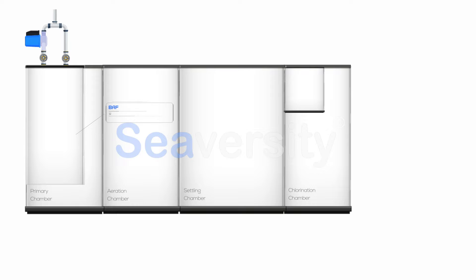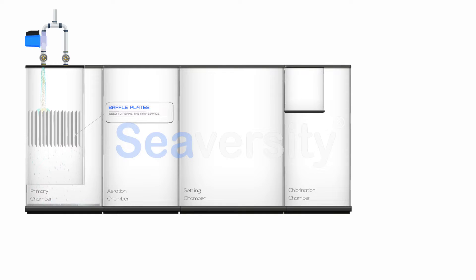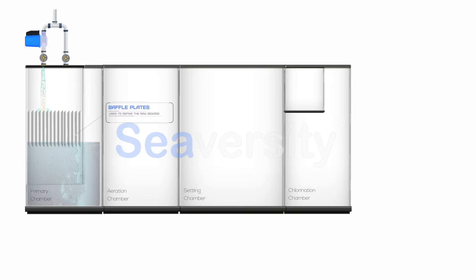The design of the primary chamber, aided by baffle plates, encourages the settling of heavier solids at the bottom and a breakdown of solid waste. This separation is crucial for the efficiency of the entire treatment process, as it prevents the overloading of the aeration chamber with solid waste. Pre-treated sewage, now with reduced solid content, is then transferred to the aeration chamber.